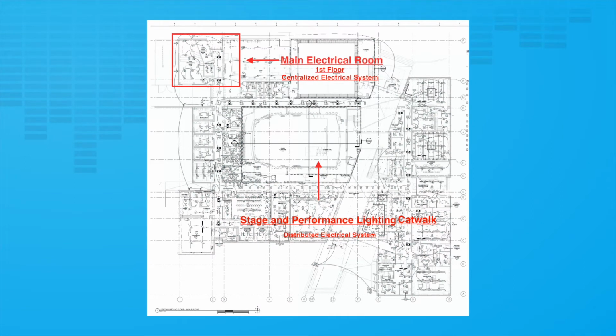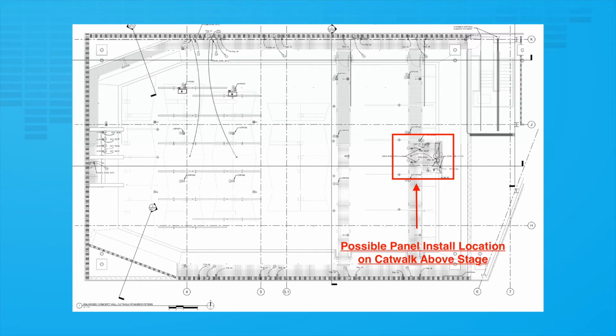Traditionally, power control systems have been relegated to electrical closets due to the size and noise generated by dimmer systems, as seen on the drawing example currently showing. Thanks to the growing popularity of LED lighting fixtures enabling designers to move away from large dimmer racks, new install areas are beginning to open up that were previously left unused, enabling controllable circuit breakers to be installed significantly closer to the end loads they're providing power to, as seen on the current drawing showing, which highlights a platform on the catwalk above the stage as a possible install location, which will significantly reduce material and labor costs.